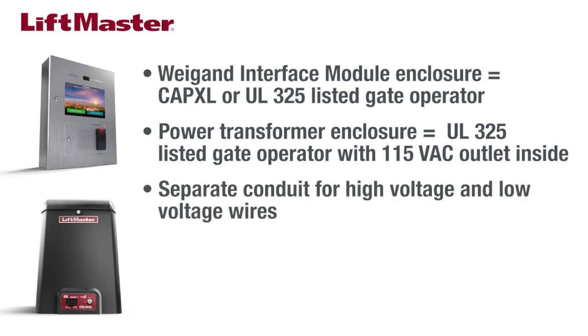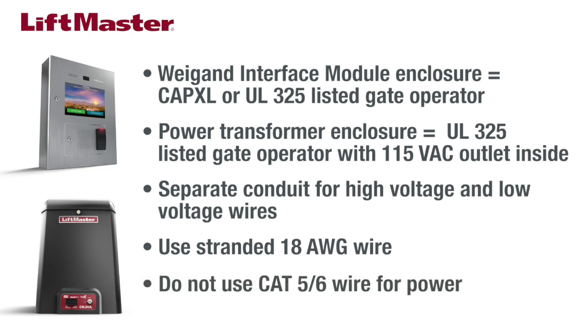Low voltage wiring connects from the access control panel to the enclosure for the Wiegand interface. Be sure to run high voltage power wiring through separate conduit from low voltage control wires. Use the proper gauge of wire. Never use Cat 5 or Cat 6 wire for power.